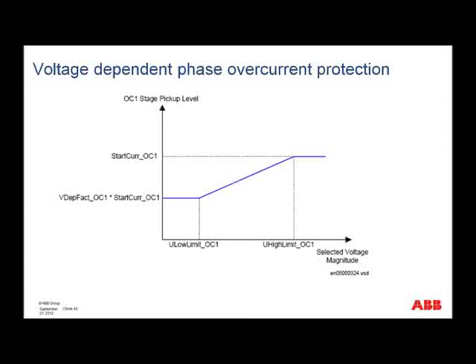So then what we do is we look at what is termed voltage dependent phase overcurrent protection. And if you look at the characteristic, here we have, this is probably around the 1 per unit voltage, where you would have the set threshold such that for maximum load current that can be produced by the generator, this threshold would then be above that. But for reduced voltage, the actual pickup threshold would reduce, and typical values for this point here is about 25% of the set value, and this point here is about 0.25 per unit as well.